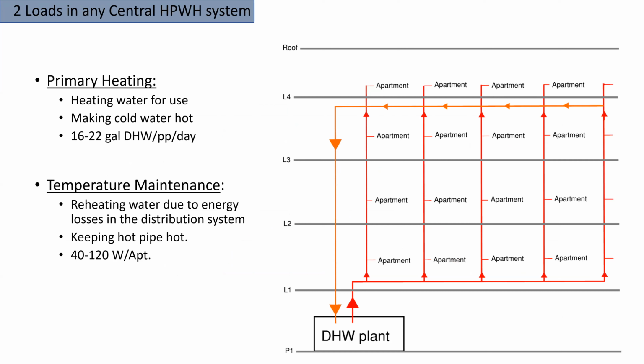To reiterate, there are two loads in any central heat pump water heating system: the primary water heating load and the temperature maintenance load. Primary water heating is just heating water for use, making cold water hot. This system is sized for around 16 to 22 gallons of DHW per person per day.